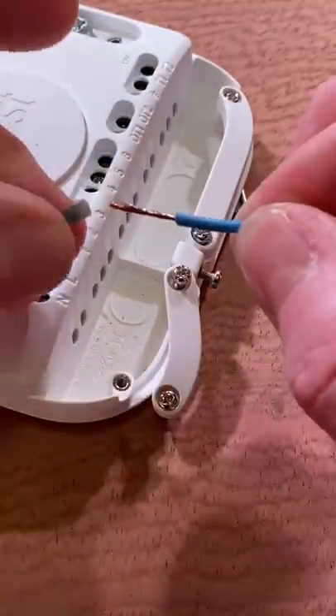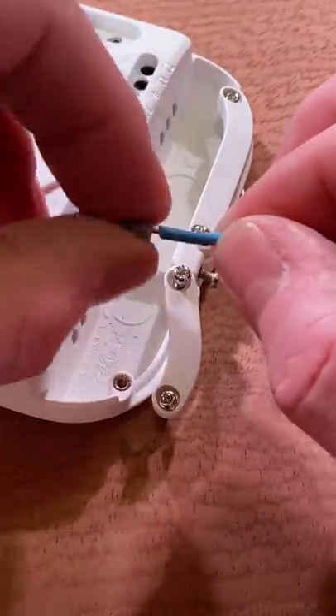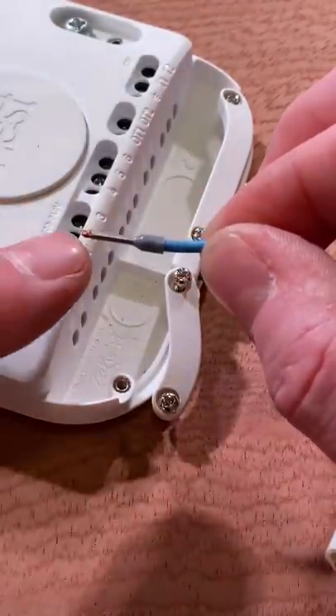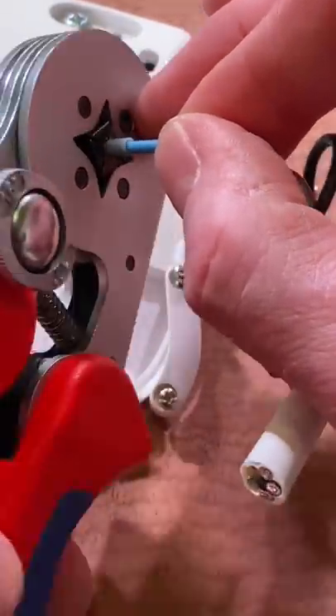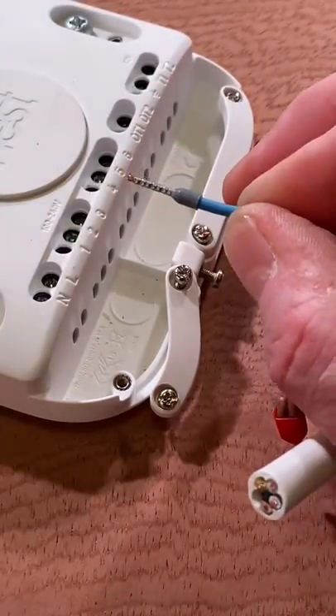Gentle twist of the conductors, introduce the appropriate size ferrule, and push it all the way down into position with some of the copper hanging over the end. Then introduce our ferrule crimping tool — in this case with a square jaw going into a cage terminal within the MK accessory.